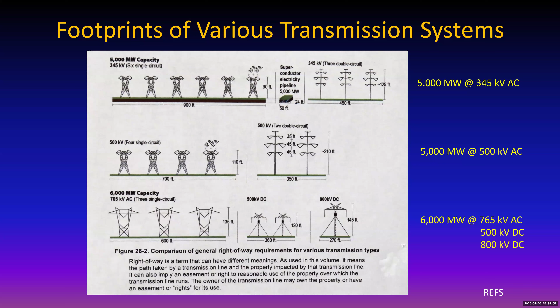They've built quite a few in the last few years. And you can see what these are. We're at 5,000 megawatts at 500,000 volts. Then we go up to 6,000 megawatts at either 765,000 volts AC or somewhere between 500 and 800,000 volts DC. And notice again, right-of-way, 600 feet for those 3 towers on the AC, 135-foot height. And the DC, half of that right-of-way, and only slightly taller, to get those lines up off the ground for safety purposes.